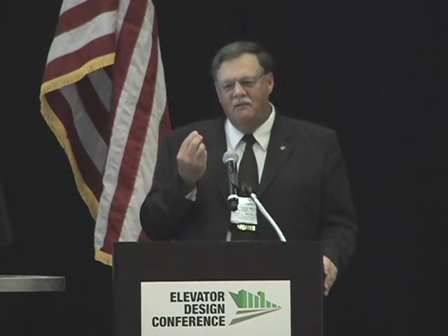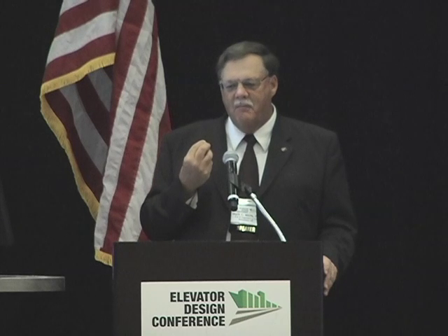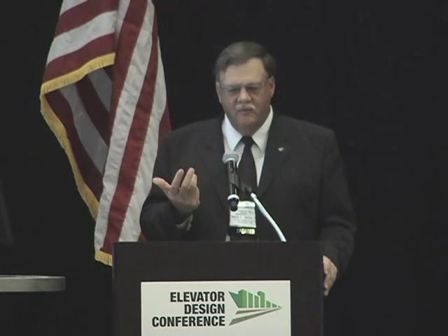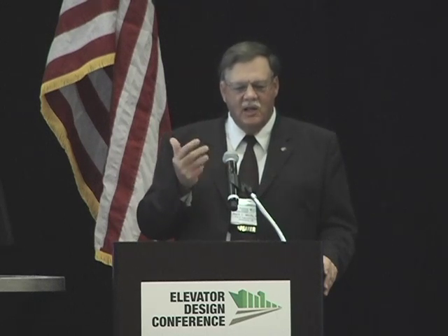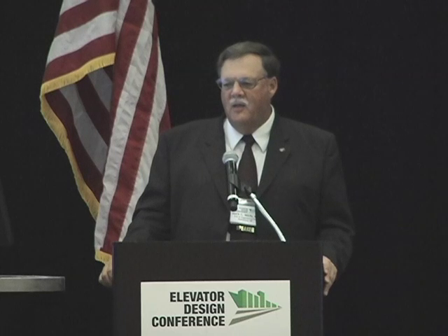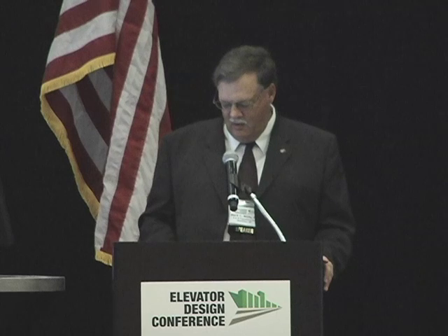Now, a lot of the soft starters today, they're getting smaller and smaller. But a lot of that's because they have built into them now a mechanical bypass. The original technology was all a solid state controller controlling your motor. Most of them have internal mechanical bypasses because once you get it up to speed, if you can bypass electronics and take them out of the circuit, it's more energy efficient itself. And you're not using the solid state circuits to run the motor, and then the duty on the solid state circuits, they can make them smaller, less expensive. A lot of them have a built-in bypass now right in the soft starter.